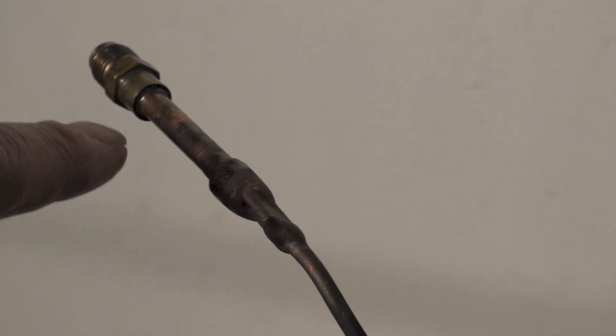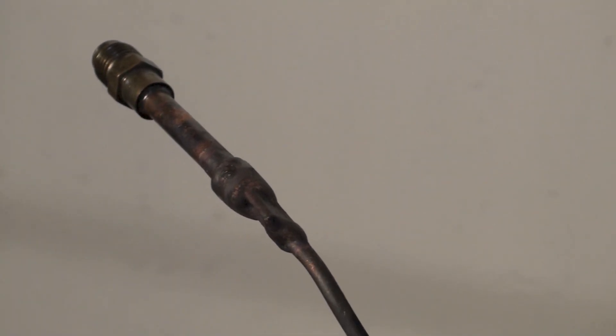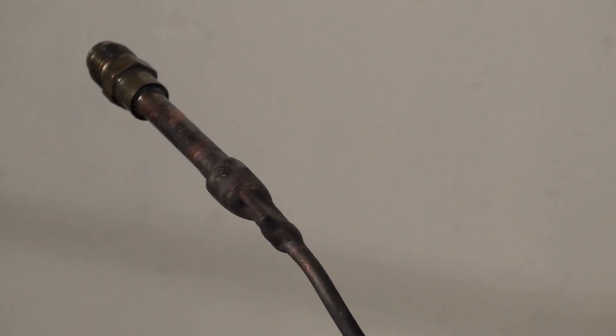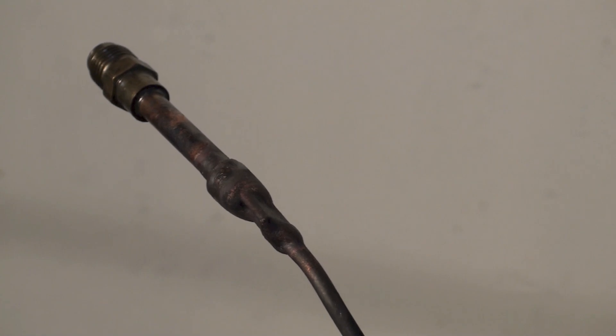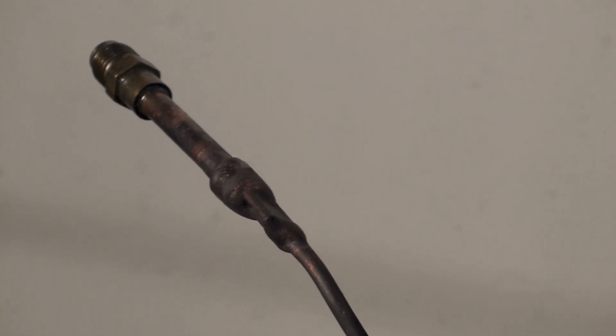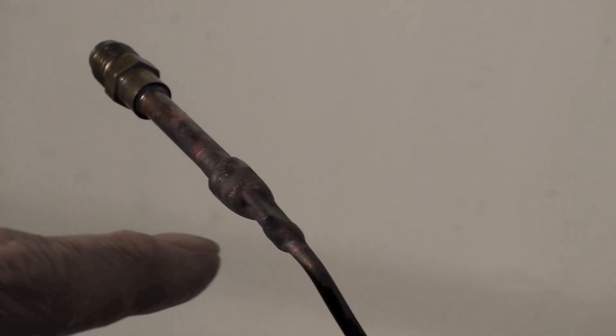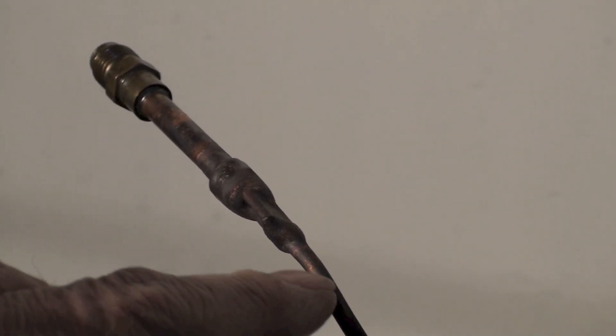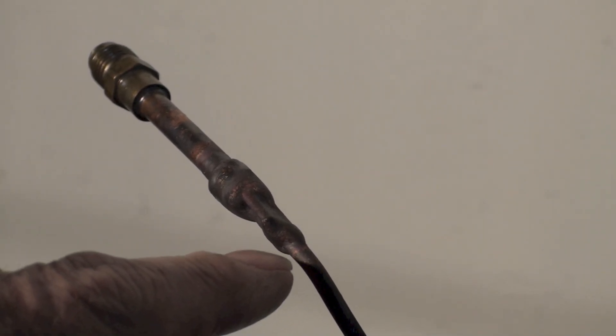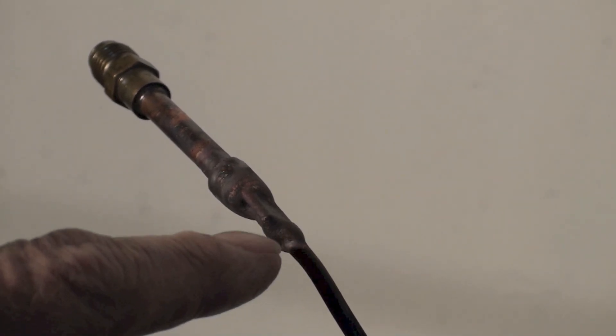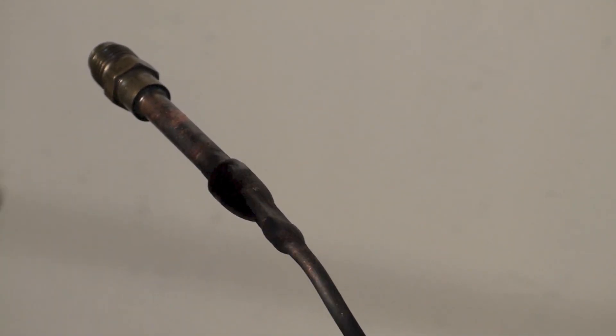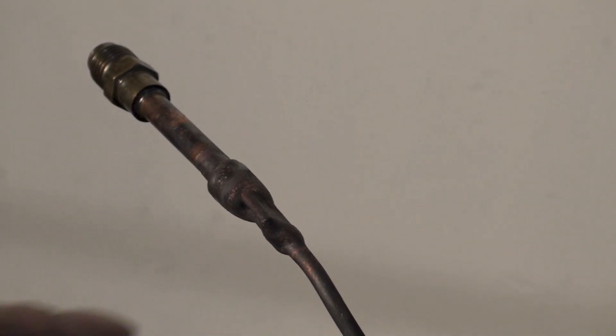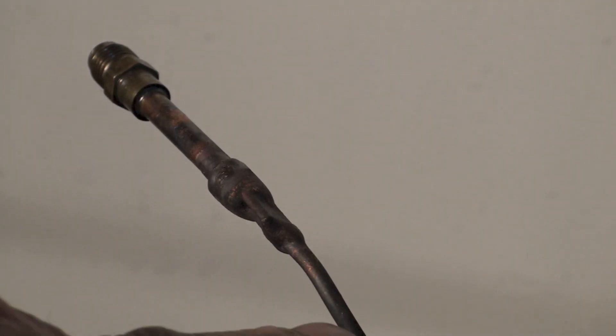One of the things I wanted you to watch is when you're doing this with an oxy-acetylene rig - it's hot - do not put any heat on the cap tube. If you put heat on the cap tube it'll just break off. See, it's the smallest piece of tubing there, it's gonna get hotter faster than anything else.